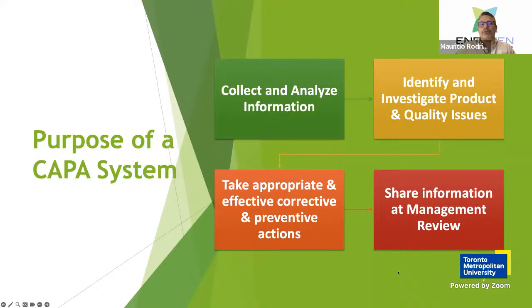So what is the purpose of the CAPA system? A good quality management system in medical devices requires a CAPA process that will collect and analyze information, identify and investigate product and quality issues, take appropriate and effective corrective and preventive actions, which will ensure the issue will not recur, and will also prevent the problem from occurring on similar products and processes. And the information collected through the CAPA system is typically shared with management through the management review process, which is a sub-process in the quality management system of medical devices.